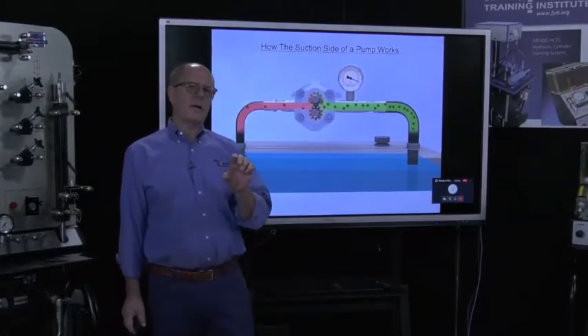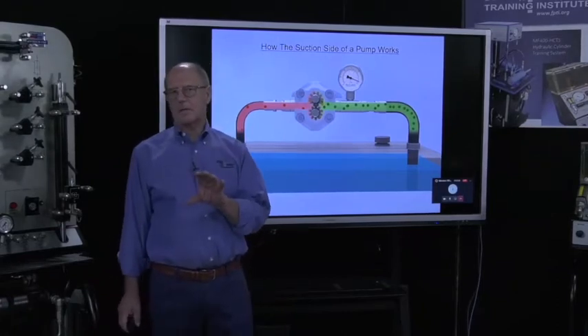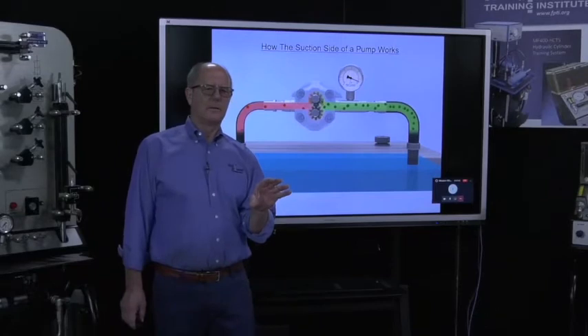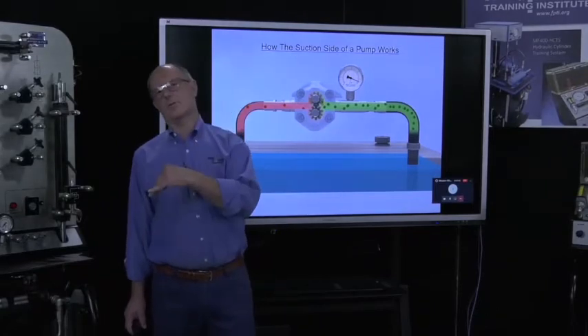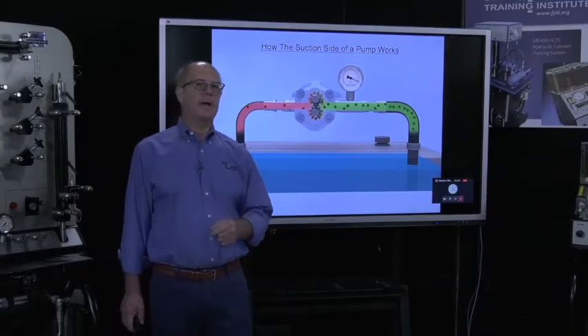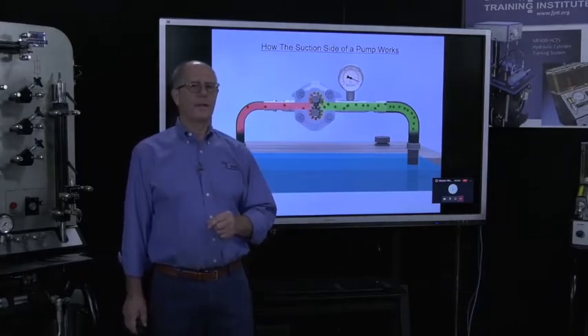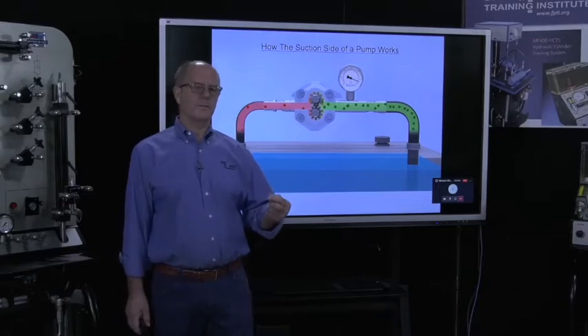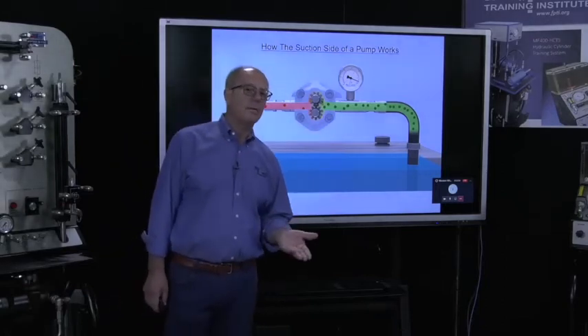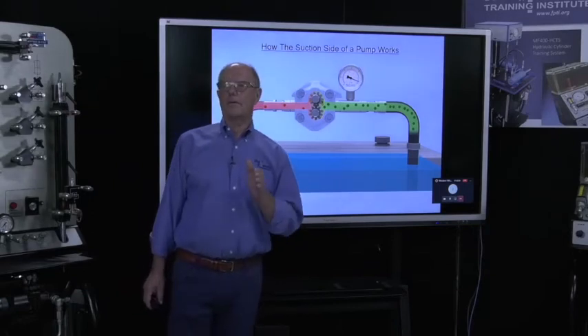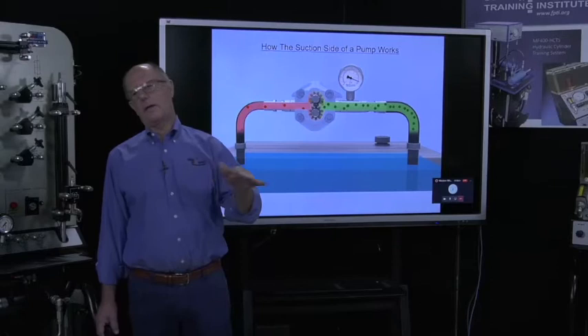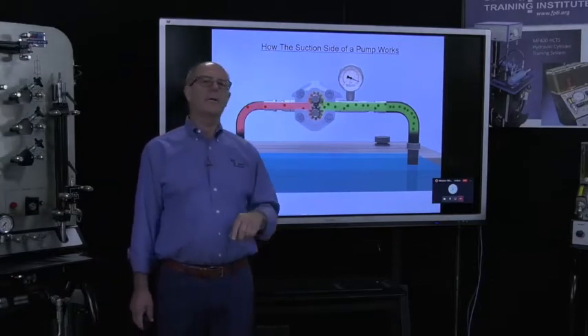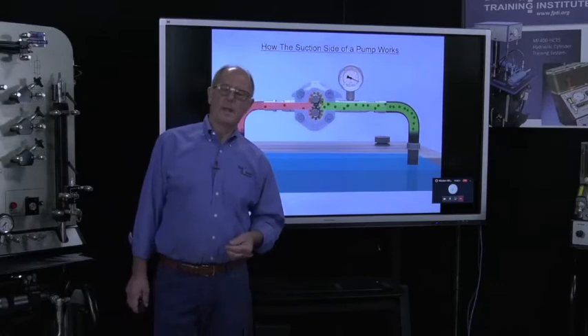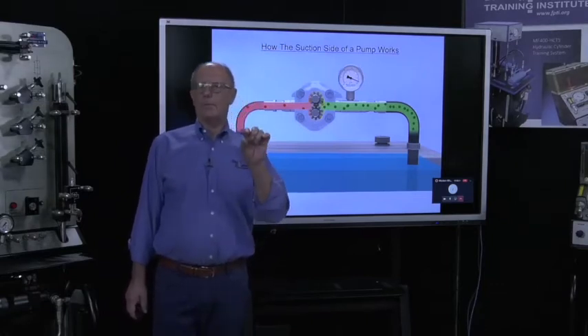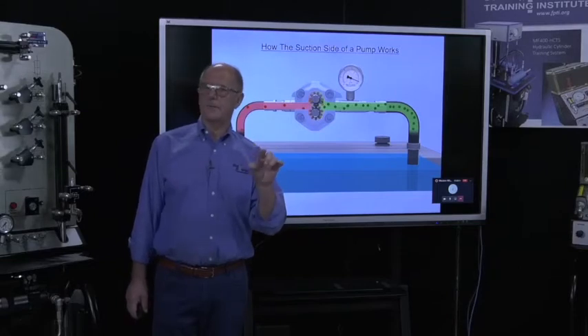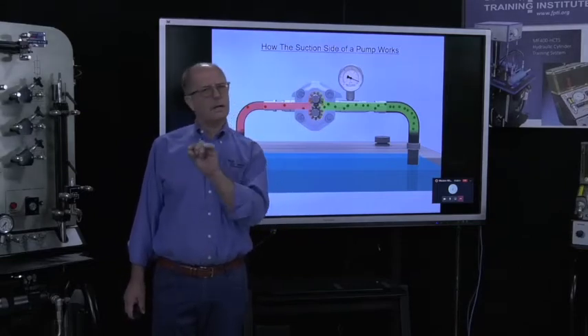If 75% of open loop pumps have signs of cavitation or cavitation that caused them to fail, couldn't that have been prevented if we were checking the inlet restriction on a hydraulic pump every 30 days based on an 8-hour shift? Now, what are you looking at when you look at inlet restriction? Well, if you read books about screens in hydraulic tanks, if you look at the disadvantages of a screen, universally, they'll tell you that you can't check them. I find that interesting. You can put an indicator on a filter head, on a return line filter or a pressure line filter, but you can't check a screen.